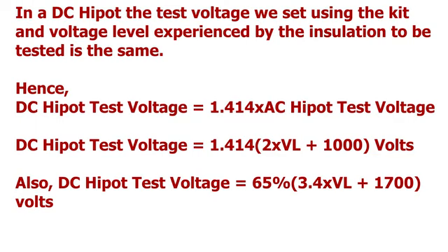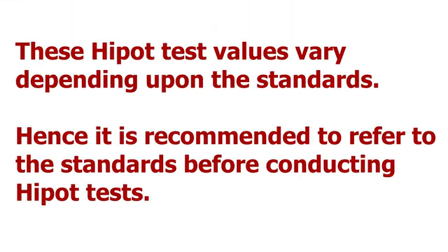Hence, in DC hipot testing, the test voltage level is raised to 1.414 times the voltage raised in AC hipot test, which is 1.414 into twice the line voltage plus 1000 volts. Also, the test voltage is taken as 65% of 3.4 times line voltage plus 1700 volts. These hipot test values vary depending upon the standards. Hence, it is recommended to refer to the standards before conducting hipot tests.